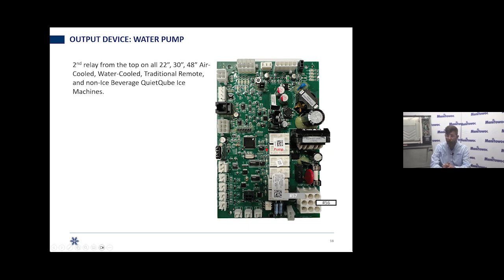Well, no water over the plate. If you go across wire 57, that gray wire, and 56, that white wire, and you've got 115 volts on a 115 volt ice machine, or 208, 230 on that style ice machine, and no water's moving, well, you've got a problem with your pump. If you have no voltage, you have a problem with that relay. At that point, you'll know which component to diagnose. Voltage to it and output device isn't operating, it's the output device. Light lit next to the relay and no voltage coming out, well, it's going to be the relay. Relays are not replaceable. Again, this will be energized during water purge, freeze, and the first 45 seconds of harvest. We do a harvest purge.